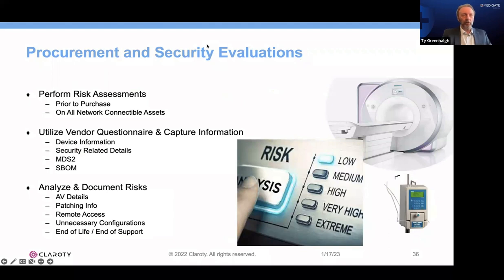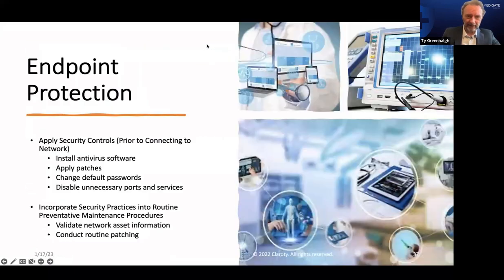Start pushing this out to your procurement, because if you can do risk assessments using these types of tools, you can stop bringing on new risk, which allows you to bail water out of your sinking boat. But if you're just bailing water without plugging the hole, you've got to stop the risk from coming in. You do that through understanding what's in the device with the SBOM and the MDS2, the manufacturer's disclosure statement for medical device security. We import those so we know what the risks are to the device, so you understand the full risk you're bringing on. You might decide to accept it, but as part of the onboarding process, you can put in the mitigations required to prevent that device from being risky before it hits the network.